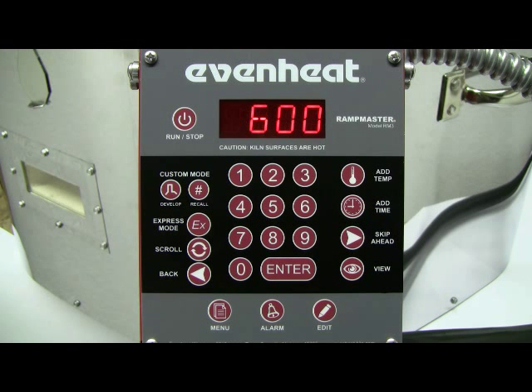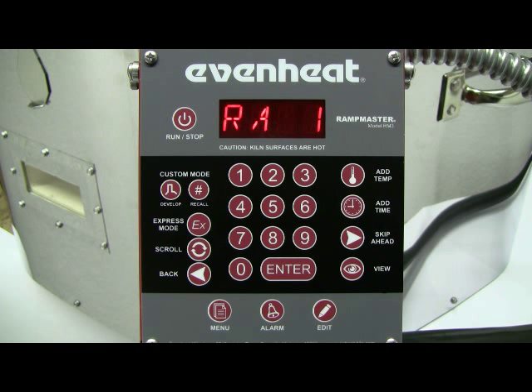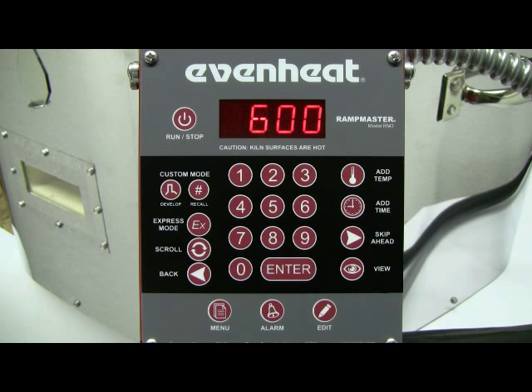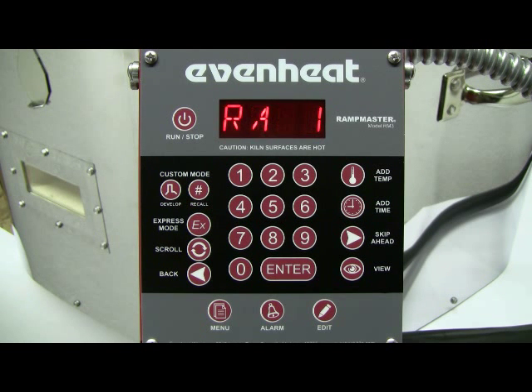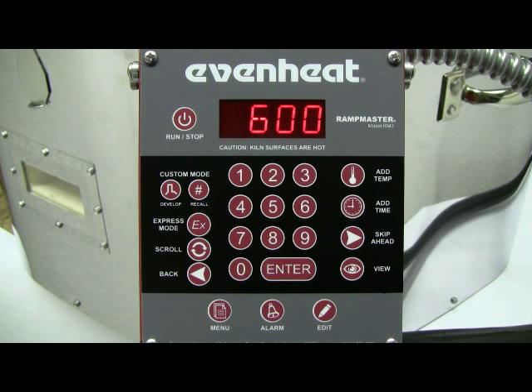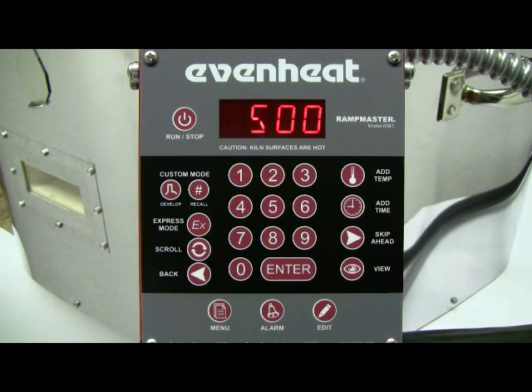The display now reads RA1. The RampMaster is asking for the temperature rate — the speed — to be used in segment 1. Rate is programmed in degrees per hour. For our example, let's use 500 degrees per hour. Type in 500, then press the ENTER key to store your choice.